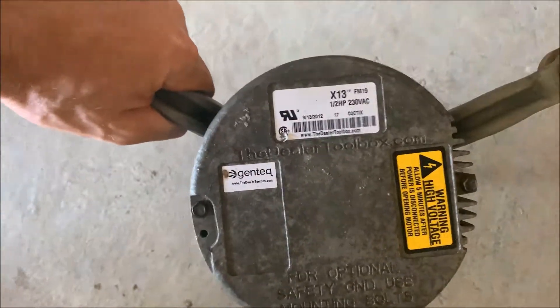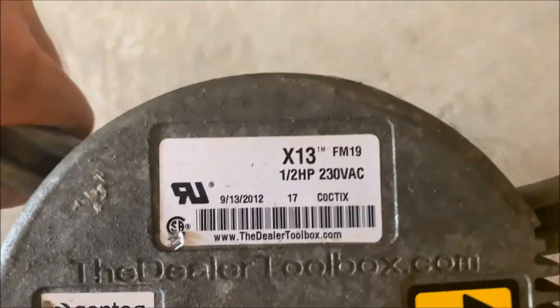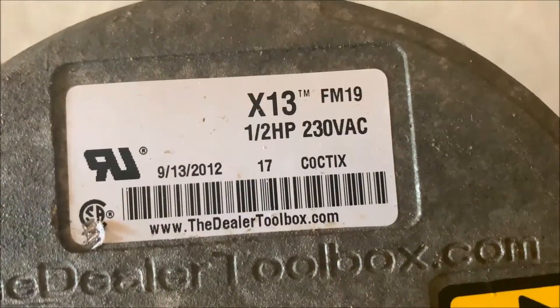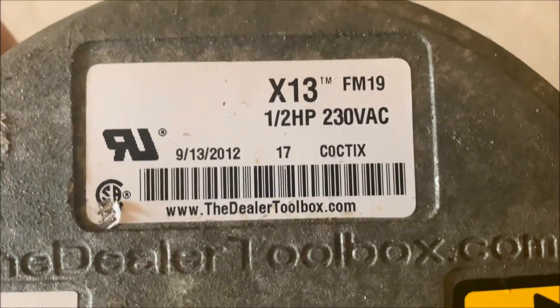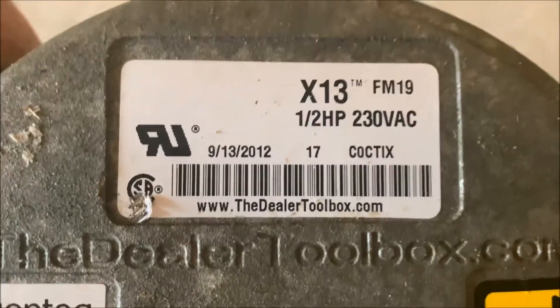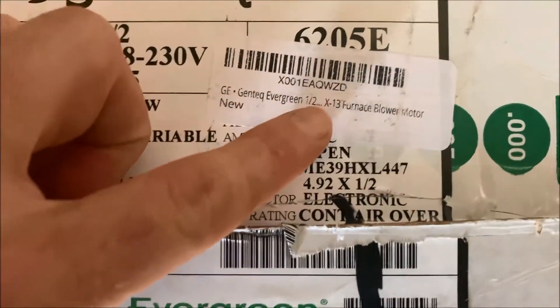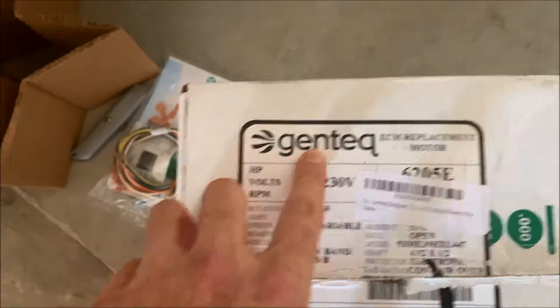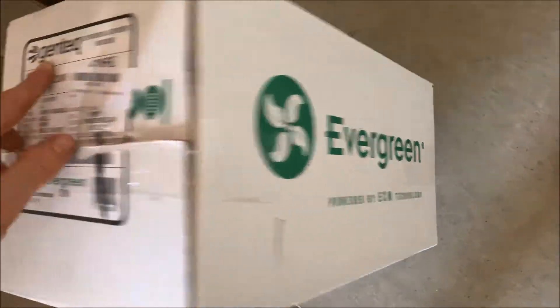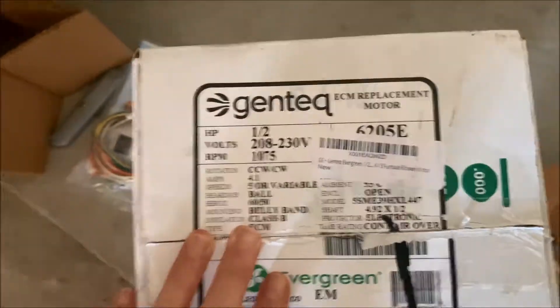I brought the motor down into the garage because it was so hot in the attic, but I wanted to show you how to order your new motor. All you have to do is look at the sticker on top. The brand is Genteq, the model is the X13, and all of those numbers are important — you want to make sure you get the exact same horsepower rating (this is a half horsepower) and it's going to be 230 volts. Here's the new motor I got off Amazon — it's the X13 replacement motor, made by Genteq, the Evergreen series. It's a half horsepower, 208 to 230 volts, so this should be a direct replacement.